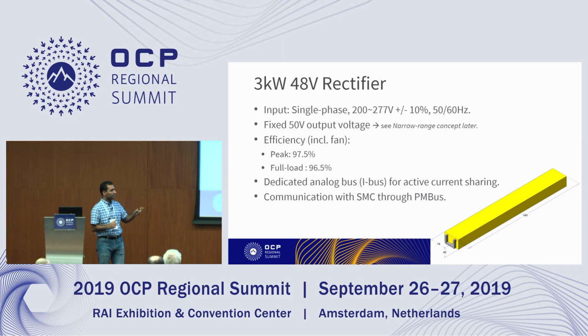The current sharing and the communication, we had a lot of good discussion there, and with a lot of you guys' support. We decided to go with the analog current sharing that we know is simpler to implement and it's more reliable. There is a droop on the rectifiers that will give 5 to 10% of current sharing, but this is with active current sharing through analog current bus. We can get up to 2-3% accuracy.